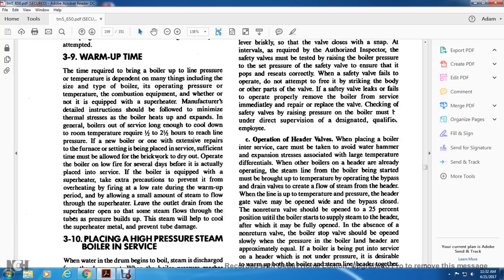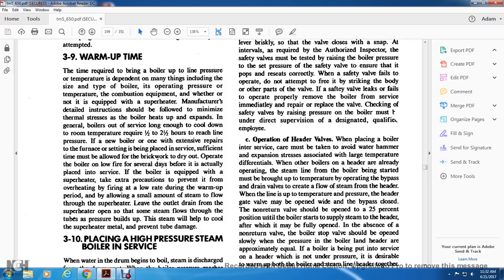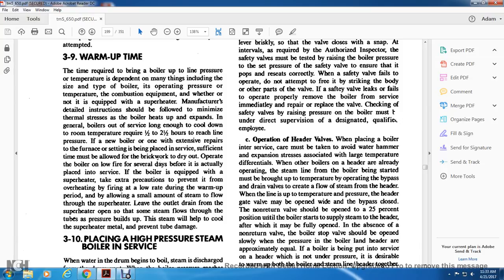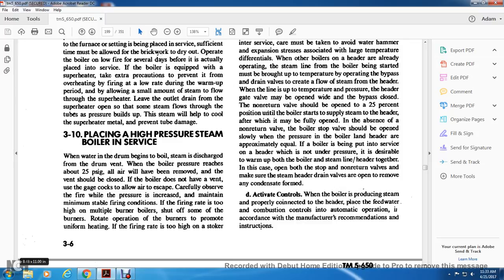Warm-up time: the time required to bring a boiler to line pressure and temperature depends on many things including size, type of boiler, operating pressure and temperature, and combustion equipment. Manufacturer's detailed instructions should be followed to minimize thermal stress on the boiler as it heats up and expands. Generally, boilers out of service long enough to cool to room temperature require one-half to two and a half hours to reach line pressure. If the boiler is equipped with a superheater, take extra precautions to prevent it from overheating during the warm-up period by allowing a small amount of steam to flow through the superheater. Leave the outlet drain from the superheater open so steam flows through the tubes as pressure builds up.